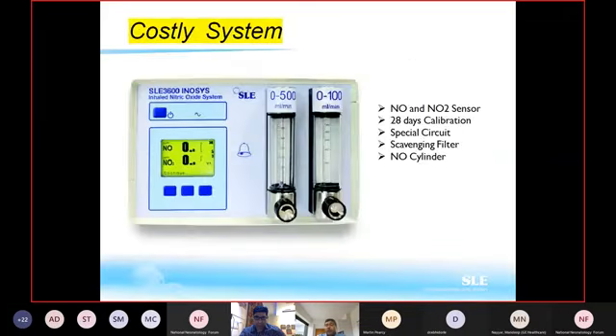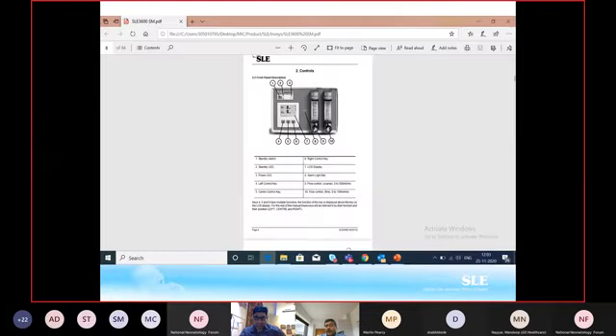In this, you will notice how the gases are being added, and then how you are taking a sample. You are giving time for the gases to mix, then you are giving time to the area where you are taking a sample to measure the NO and NO2 concentration, and then it's being added to the humidifier, and then goes to the patient. Then after that, you can see how it's being taken out through the scavenging filters from the SLE 5000, so that you are neutralizing the overall thing.